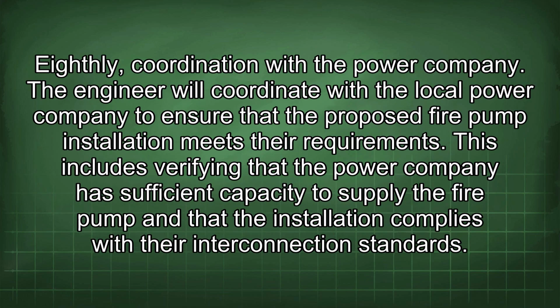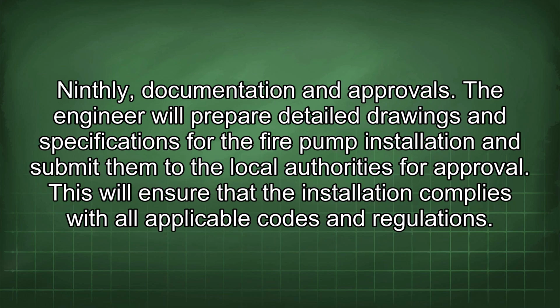Eighthly, coordination with the power company. The engineer will coordinate with the local power company to ensure that the proposed fire pump installation meets their requirements. This includes verifying that the power company has sufficient capacity to supply the fire pump and that the installation complies with their interconnection standards.